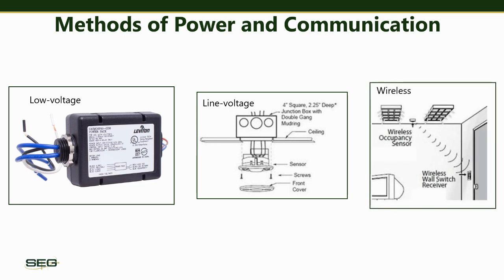Lastly, wireless. Wireless sensors have rapidly gained popularity, particularly for upgrades of existing lighting. Sensors and controllers communicate using a wireless method such as a dedicated radio frequency. The sensor can be installed anywhere within range and transmits to a controller, typically installed on or in a luminaire or on a junction box, which then controls the load based on its algorithm. The sensor may be powered by an internal battery or even a solar cell, and these sensors can also be networked.